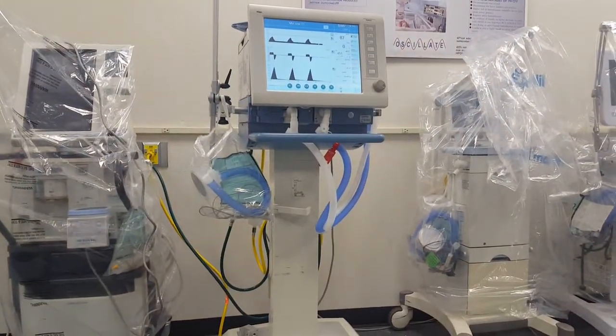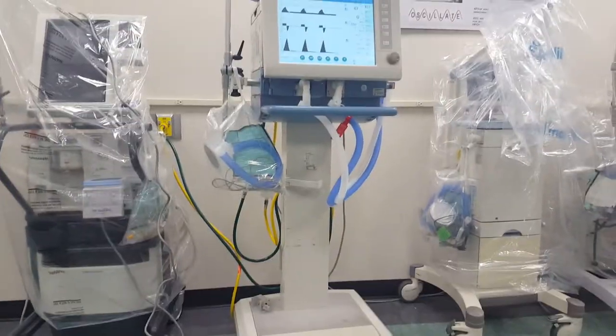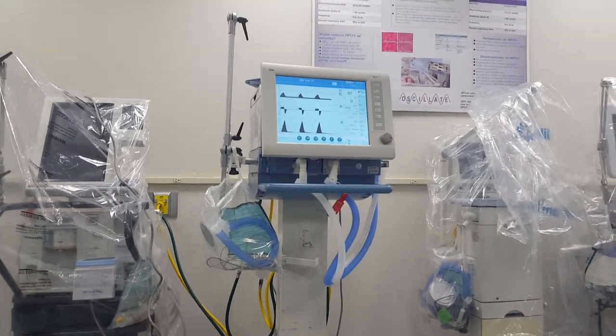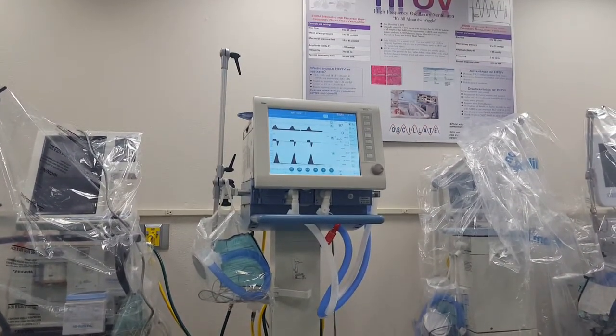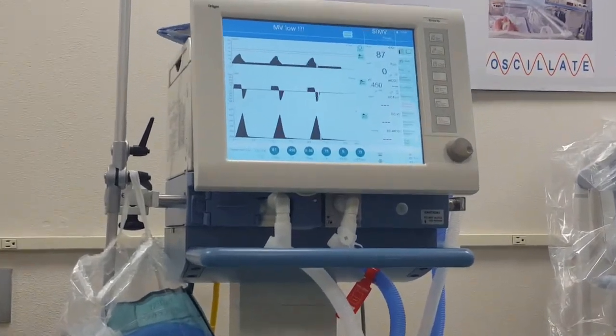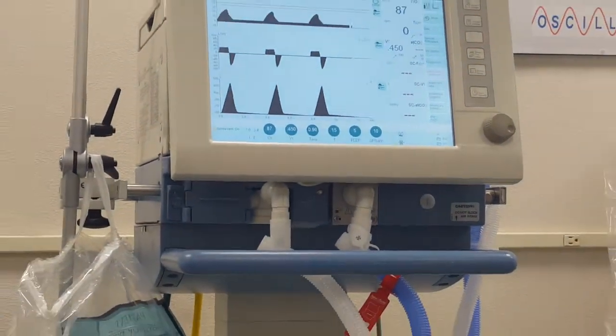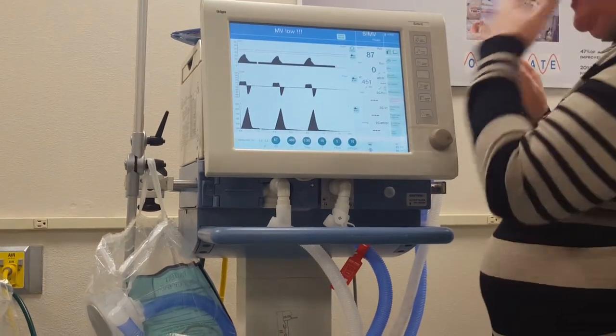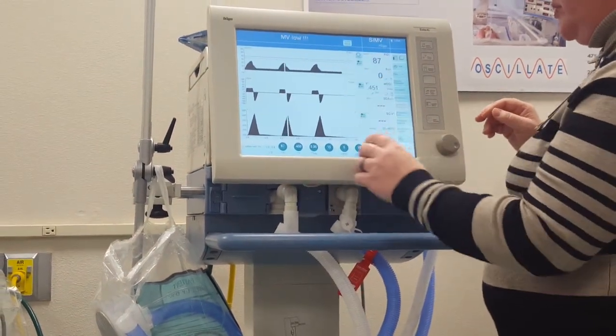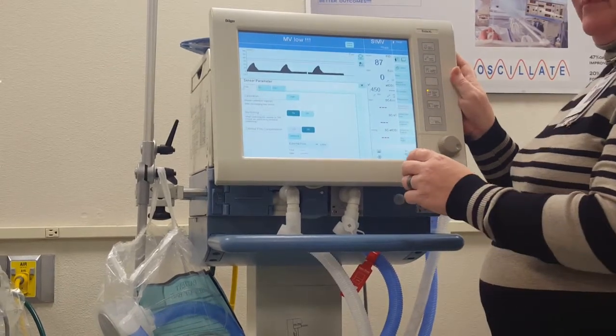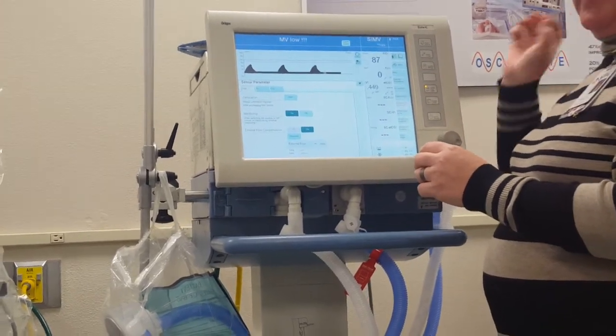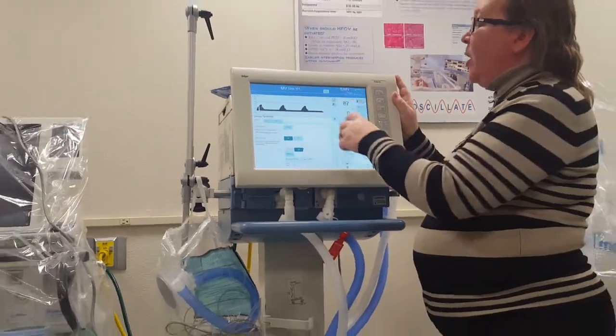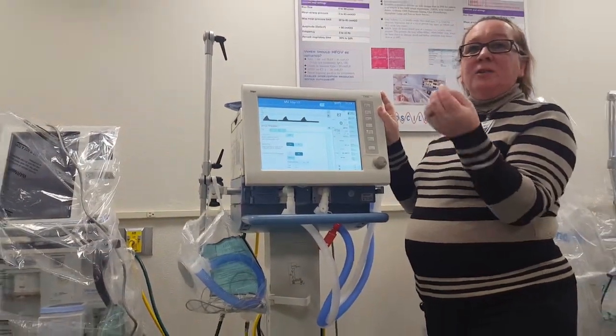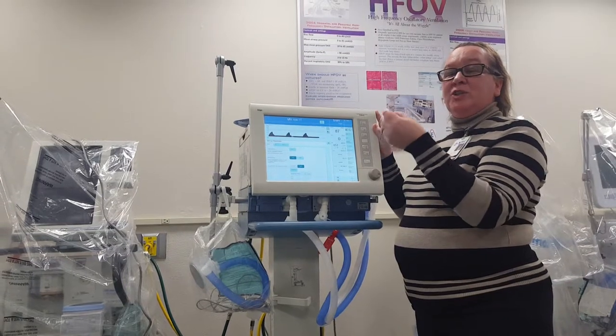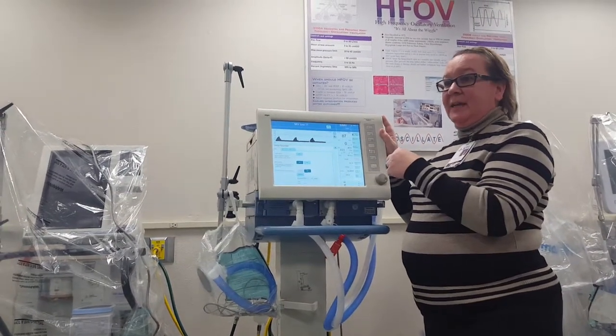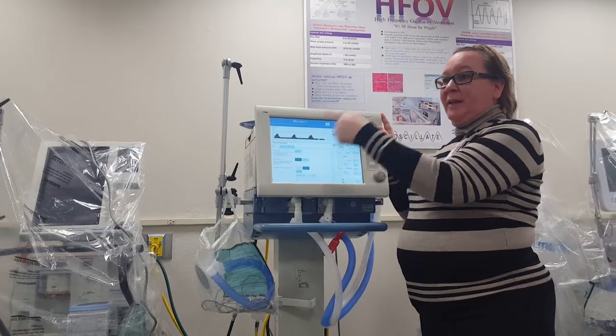Yes. So just want to get this right, or double check. To get your plateau, you have to go to inspiratory hold, expiratory hold, and then freeze it, and then you turn the dial to paw, and that's how you get plateau. You move the dial to where you see the flat line. Let me do it one more time. So this paw is different from the paw in the alarms. It's the same pressure setting. Yeah, it's a little confusing. Let me clarify: on the DRAGER, mean airway pressure is listed as P mean. And if you see paw other places, it's just talking about a regular pressure.